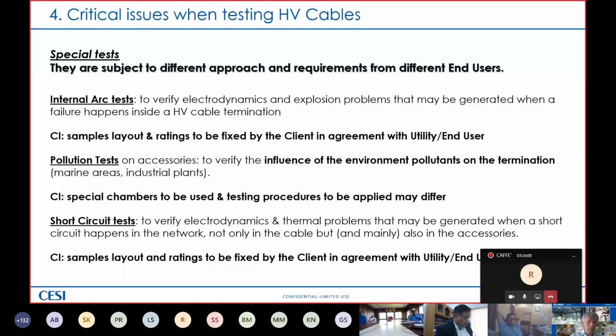Talking about a short circuit test, to verify electrodynamics and thermal problems that may be generated during a short circuit that happens in a real network. This is done not only to check the cable, but also the accessories. And again, the layout and the ratings have to be fixed in agreement by our client and the end users.